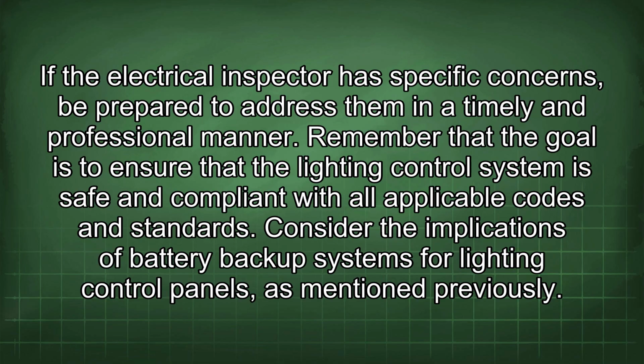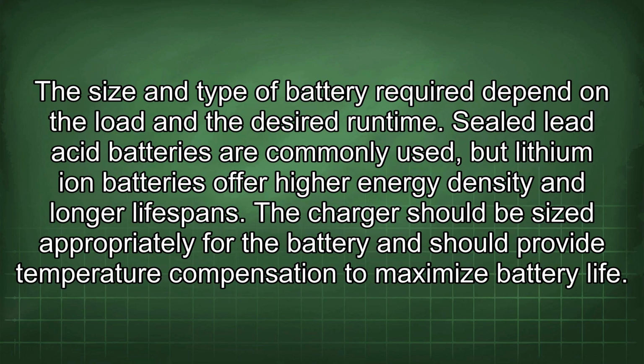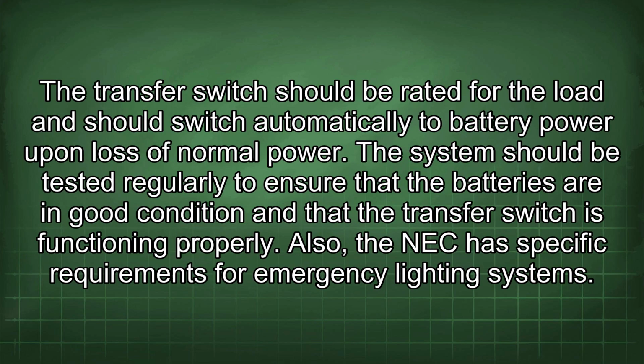and standards. Consider the implications of battery backup systems for lighting control panels, as mentioned previously. The size and type of battery required depend on the load and the desired runtime. Sealed lead-acid batteries are commonly used, but lithium-ion batteries offer higher energy density and longer lifespans. The charger should be sized appropriately for the battery and should provide temperature compensation to maximize battery life. The transfer switch should be rated for the load and should switch automatically to battery power upon loss of normal power.